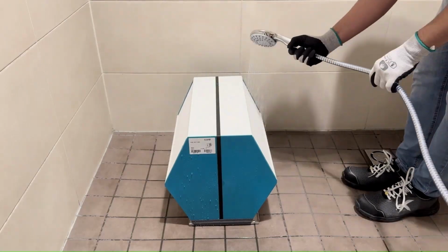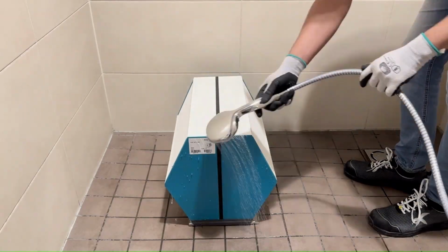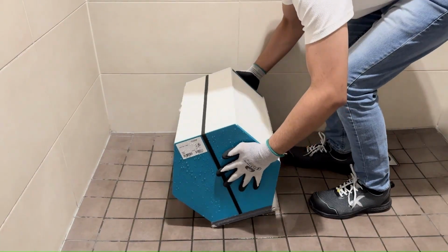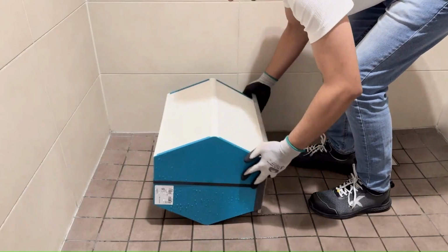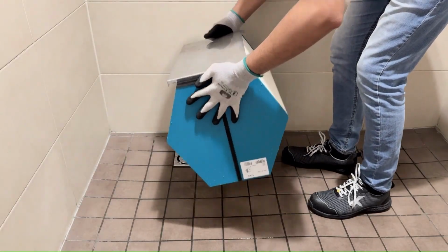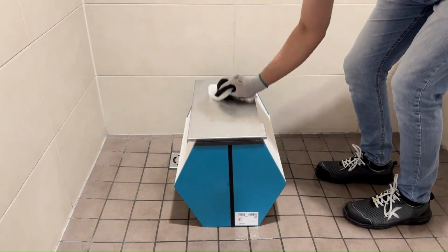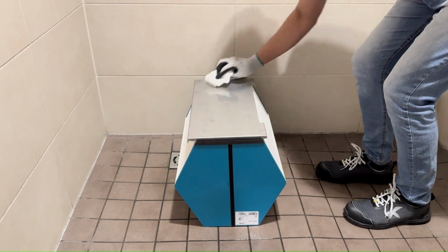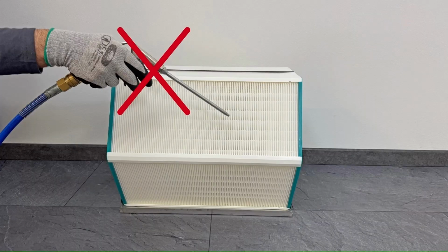Clean the counterflow heat exchanger by rinsing it with lukewarm water. After rinsing, ensure that any residual water is drained from the counterflow heat exchanger. Finally, wipe it with a soft cloth and allow it to dry briefly before reinstallation. Avoid aggressive cleaning agents and never use compressed air, as it may damage the heat exchanger.